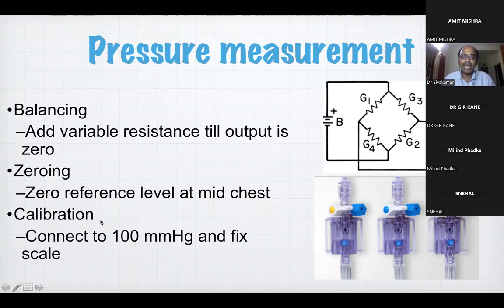And the third one is calibration. Today, in the majority of cath lab machines, it's auto-calibrated. Otherwise, in the past, they used to give a 100 millimeters mercury flick. A button is pressed and immediately it goes to 100. Then you check whether it is at 100. Today, there is no separate calibration because all the machines are auto-calibrated. So the two things that we need to know are what is called balancing and what is called zeroing. Zeroing is moving the transducer up or down.